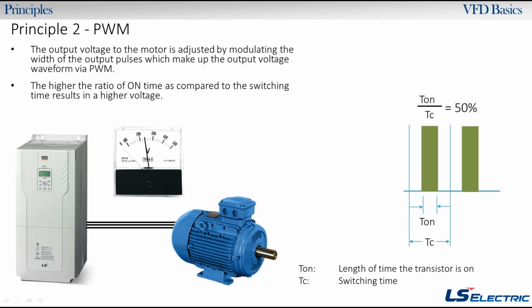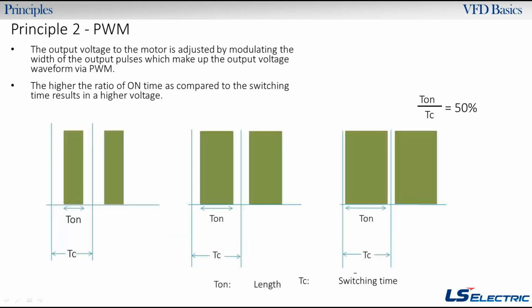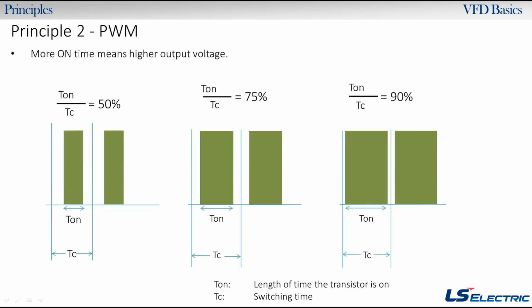Okay, so this one is 50% is what they're showing here. That'd be like 50% voltage, or like 230 volts on a 460 volt output, for example. So here's the one we're just showing, the 50%. If you modulate that width, so this goes back, we're modulating the width of the pulses. That's where they came up with the name PWM. Extend that out, now we're at 75%. Extend out that T on time more, 90%, and then it could always extend out more. So again, length of the time the transistor's on versus the total switching time. That's what we're talking about here.